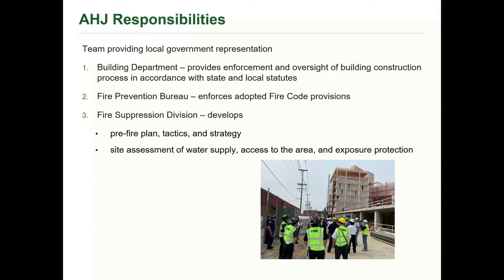So nobody's watching. And it's not because the fire inspectors are lazy, and it's not because the building inspectors are lazy or negligent. They're just retreating into their traditional roles. Because building inspections are permit driven and fire inspections are permit driven or complaint driven, there's no administrative mechanism to really trigger construction fire safety inspections. I've been on both sides of it, in building departments and in fire marshal's offices. I think that's why this is a challenge, because of this, what I call the responsibility gap.